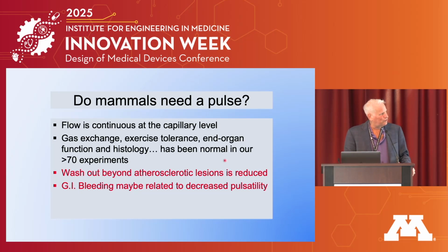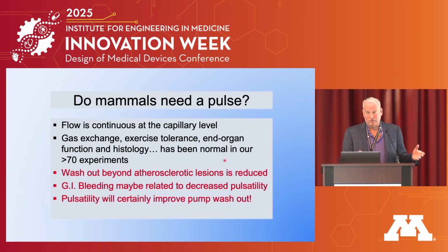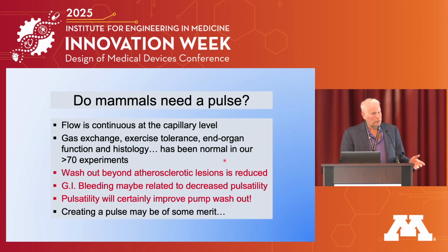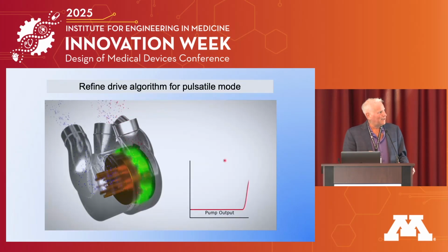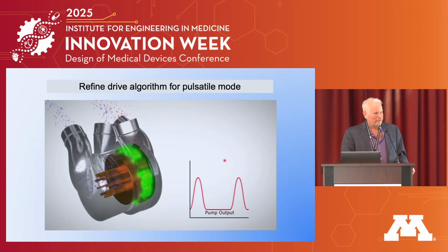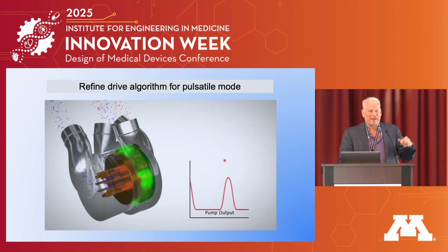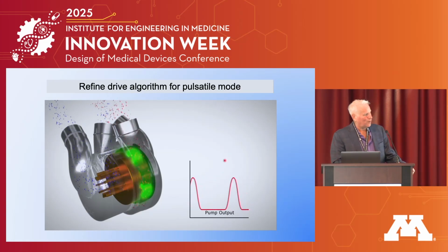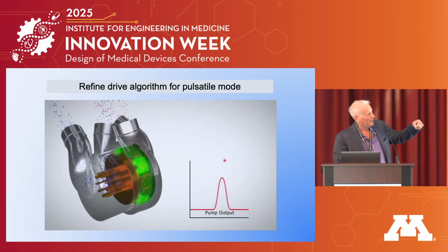There's a lot of research that's going on. And a pulse will certainly help us wash out the device. The flow through the pump will be changing every time we do a pulse. So creating a pulse may be of some merit. Well, this is a digital pump. We can make any waveform we want. In fact, we now have it so it makes a dicrotic notch, so it looks like a regular arterial waveform, just by speeding up and slowing down.